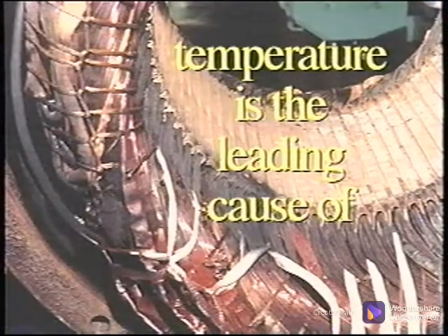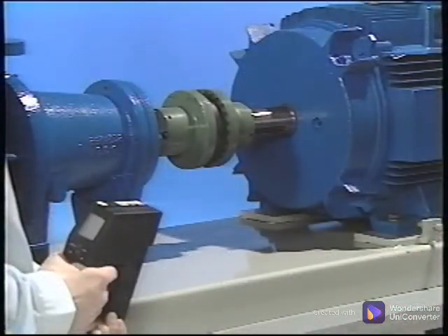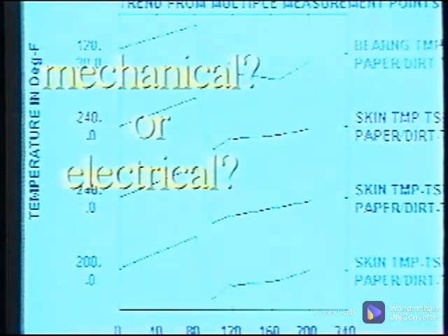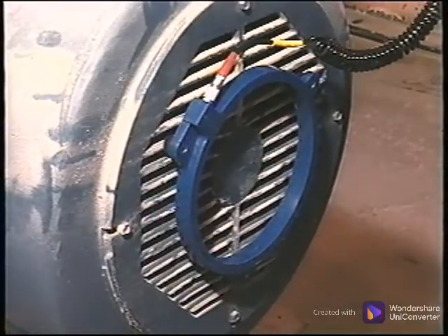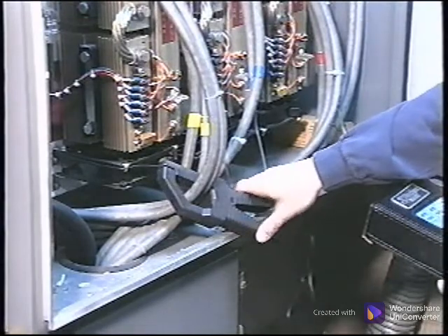Since temperature is the leading cause of insulation breakdown and therefore motor failure, make temperature measurements to determine whether there is airflow blockage or whether there is a mechanical or electrical problem adding heat to the system. By combining these technologies, your motor analysis capabilities will be maximized.